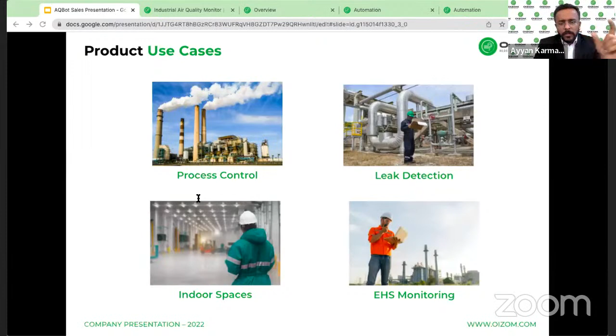The first one is AQBot SO2. Sulfur dioxide becomes a key parameter when it comes to industry. The ranges on offer are 0 to 20, 0 to 100, and 0 to 1000 for every parameter. SO2 works on the principle of electrochemical sensing - we decided to work on that principle. You may ask why, and the answer is that over the last 5 or 6 years, our R&D team has been working with different working principles, and we identified this to be the perfect working principle for SO2. In a similar manner, every working principle you'll see from here has been identified by our team.